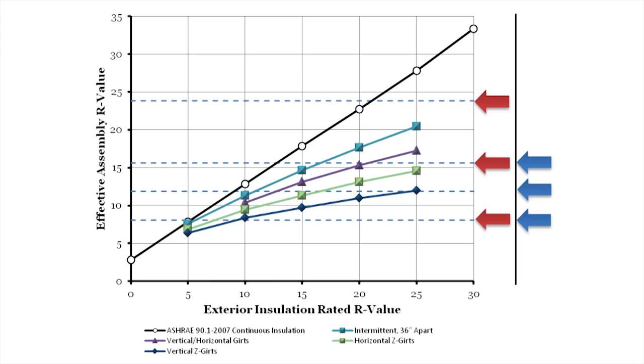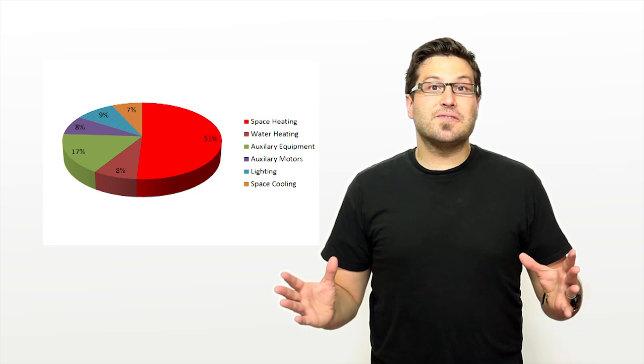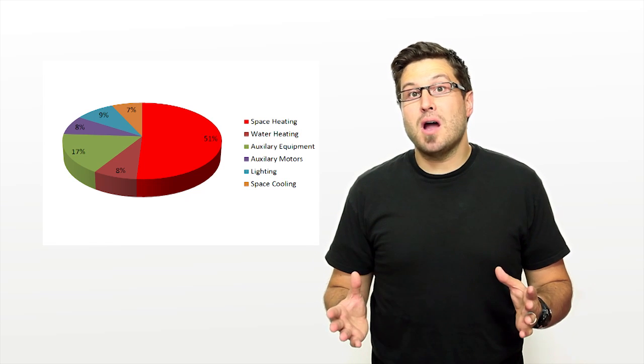When we looked at alternate clip systems, we found that very simple solutions like using intermittent Z-girts or clips instead of continuous ones could easily improve overall thermal effectiveness by 50%. This finding is important because in modern buildings, approximately half of all energy consumed is in heating and cooling, and the walls are the biggest source of thermal transfer.